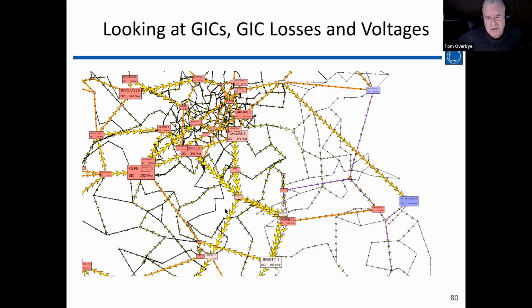Yeah, and that's a great question. I don't have to go to slide 9 because you're just asking about the restoration issue. What we would do is simulate an event, and it depends on the size of the HEMP. In some of the public waveforms, like from the Ditcher document, there's not going to be any rebuilding because nothing got damaged. In terms of damage to the transformers, we can do a heating analysis on them. I didn't talk about that here, but we've done that for GMD. The transformer heating depends upon the GICs going through the transformer, and if the transformer is damaged, then you're going to have to replace it, which is a more involved process.